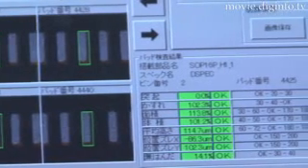Using a CCD camera placed perpendicular to the object being inspected, the machine uses a projector to radiate a color-stripe light pattern onto the object. The camera then picks up any deviations in this pattern. This method makes inspection speed faster, and fine pitch pads of up to 8 microns can be inspected at high levels of accuracy and repeatability.